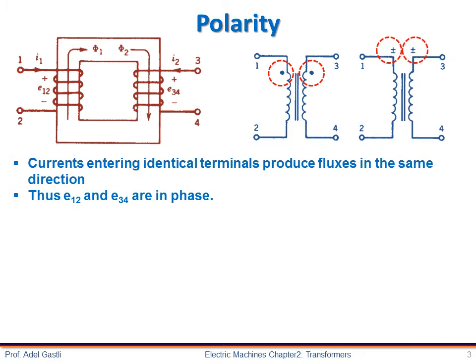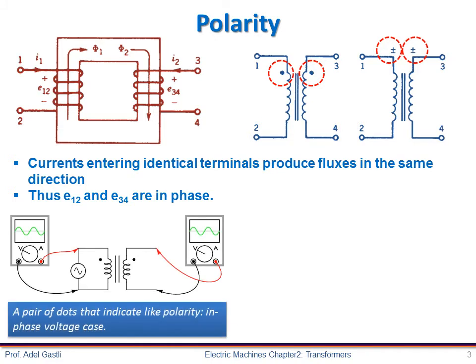Since this is a practical concern, transformer manufacturers have come up with polarity marking standards to denote phase relationships. It is called the dot convention, and is nothing more than a dot placed next to each corresponding leg of the transformer winding. The similar placement of these dots next to the top ends of the primary and secondary windings tells us that whatever instantaneous voltage polarity is seen across the primary winding will be the same as that across the secondary windings — in other words, the phase shift from primary to secondary will be 0 degrees.